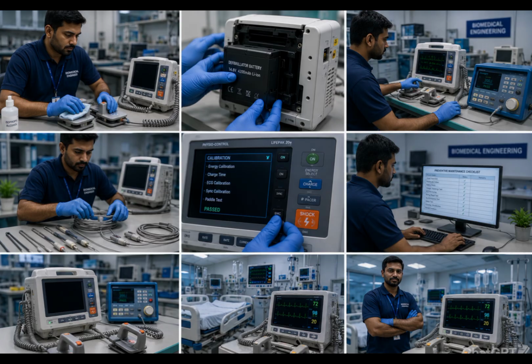And the next one is not a problem, but you have to do it properly. That is preventive maintenance. If you don't do preventive maintenance regularly, then you might face a problem. Regular maintenance improves equipment reliability. So what you should do now? Clean the paddles regularly and inspect the electrodes. Check the battery health. Every time after usage, cables should be organized properly. Do energy output testing and calibration verification as well. Use a defibrillator analyzer to test shock energy accuracy. Record all the maintenance results in the service checklist.